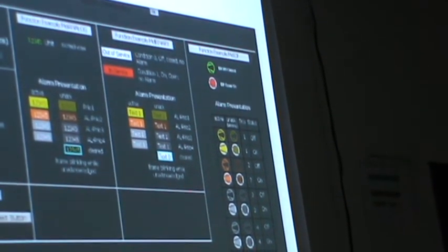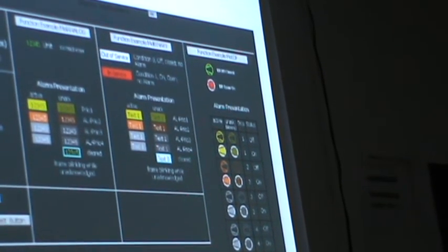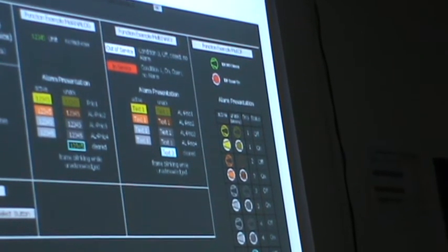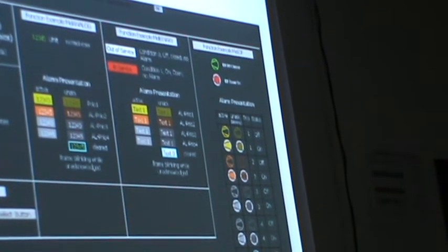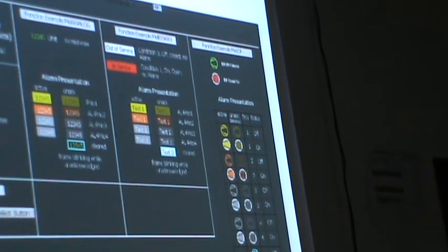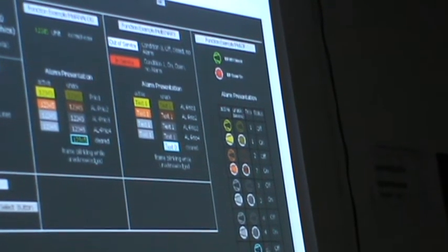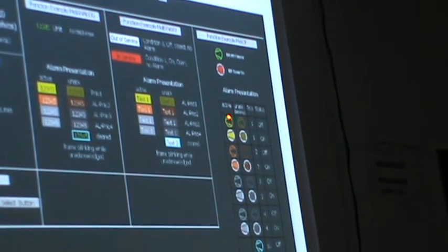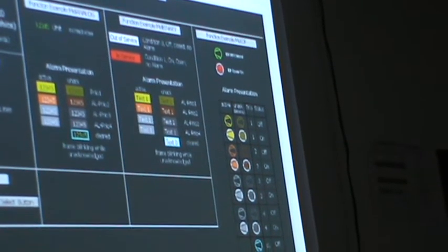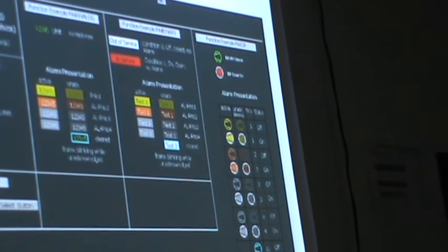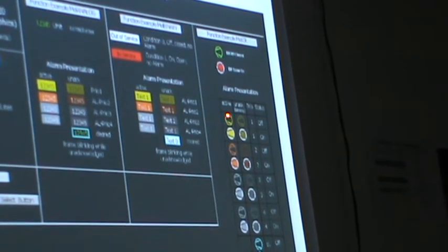If it trips, the pump was normally in running condition, and if you are getting some alarms, you will get this kind of indication. And in stop, like when your emergency push button is pressed in the field and the pump is not started, it is in a safe condition. So in that condition, you will get this kind of color. It means your emergency push button is pressed, you need to release it and then start the pump. The same has the priority, but this is not used here. Only this yellow color we use for the pumps.